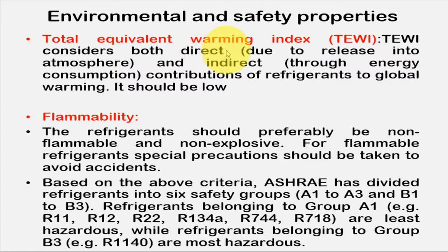Next is total equivalent warming impact, TEWI. It considers both direct and indirect contribution of the refrigerant to global warming, and this TEWI should be low. Direct means due to release into the atmosphere, and indirect means through energy consumption. Then the refrigerant should be non-flammable and non-explosive. The flammability of a refrigerant is because of the presence of hydrogen.